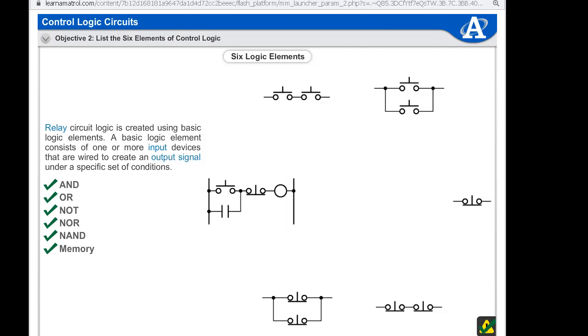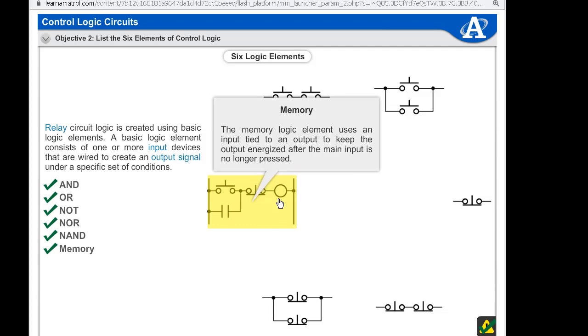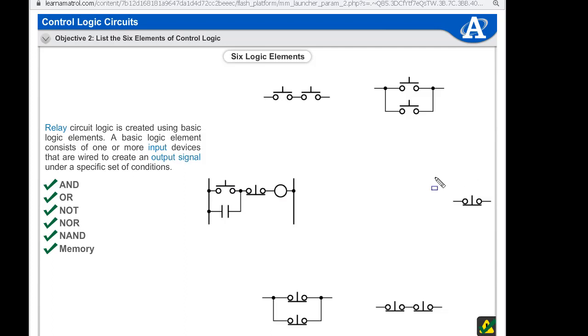Know the components of a ladder diagram. We have inputs, outputs, we have the rungs and the rails, and then we have the wires in between. Remember the deal about ladder diagrams too, that for example here we only have one output per rung, so if we want a second output we can't put it here. We have to draw a parallel branch down here. Let's see if we can get the marker working, and we'll put another coil here and then we'll come back up. So make sure we don't want to put a coil over here because this actually causes a voltage drop if we put 2 of them in there, so remember that.